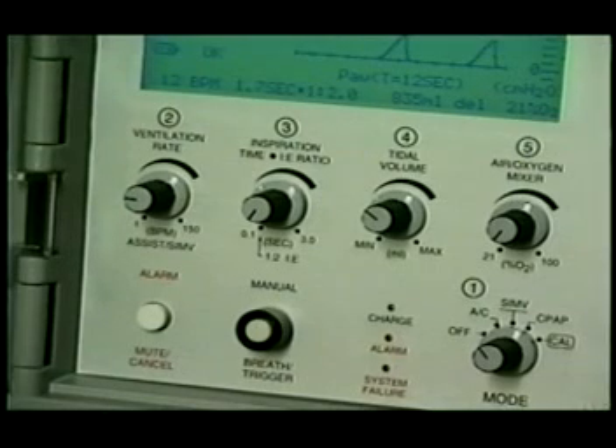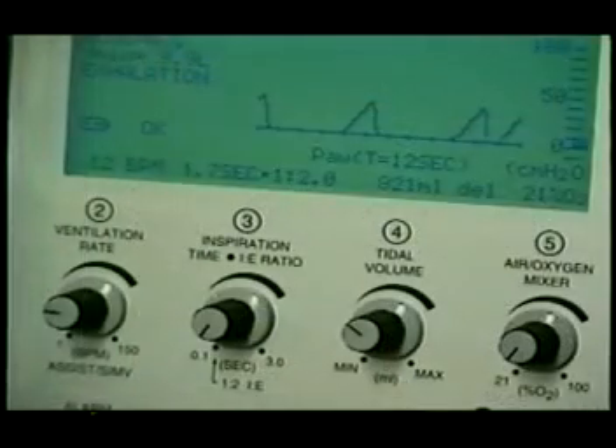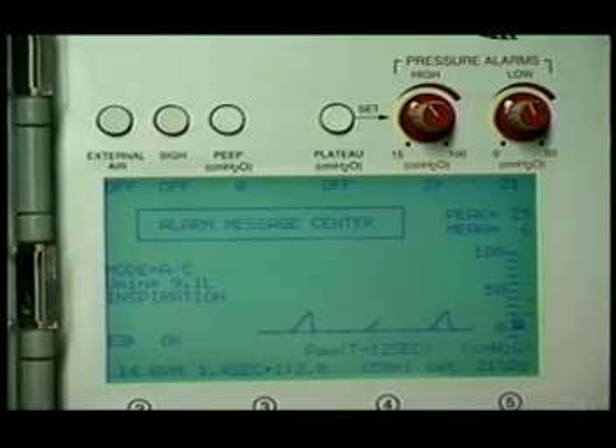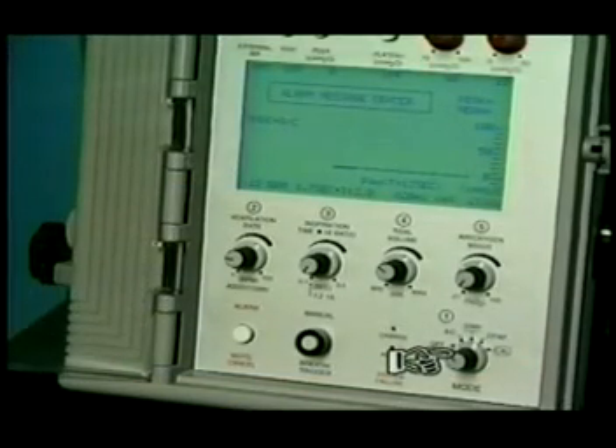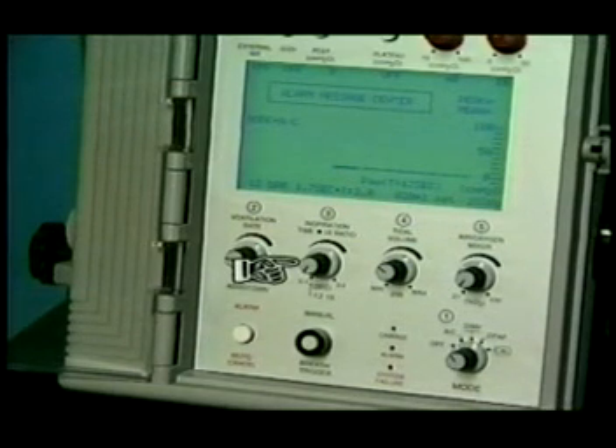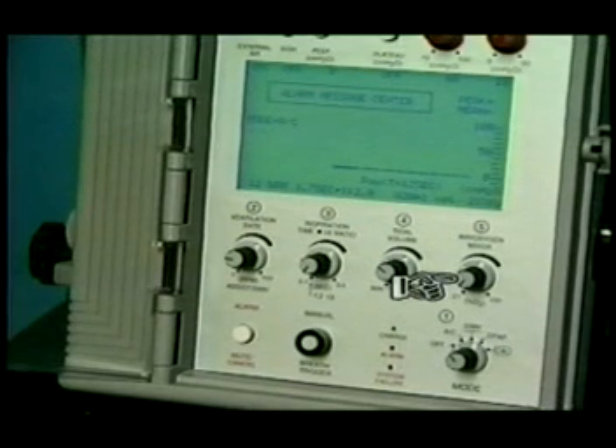The front panel contains 5 numbered controls: the mode select switch, the ventilation rate control, the inspiration time, I:E ratio control, the tidal volume control, and the air oxygen mixer control. The normal sequence of operation contains 5 steps. This means that a minimum number of control adjustments must be made to begin operation: 1, 2, 3, 4, and 5. The settings for controls 2, 3, 4, and 5 are displayed immediately above each control on the LCD panel. The setting for each push button and control located above the LCD is displayed across the top line of the LCD. To begin operation, set the operating mode, the ventilator rate, the inspiration time, I:E ratio, set tidal volume, and then the air oxygen mixer.